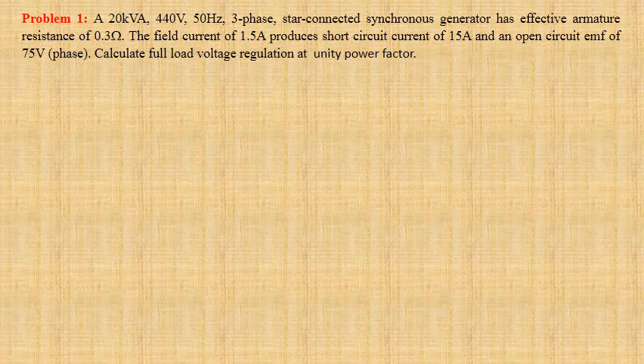A 20 kilovolt ampere, 440 volt, 50 hertz, three-phase star connected synchronous generator has effective armature resistance of 0.3 ohm. The field current of 1.5 ampere produces short circuit current of 15 ampere and an open circuit EMF of 75 volt per phase. We have to determine full load voltage regulation at unity power factor.